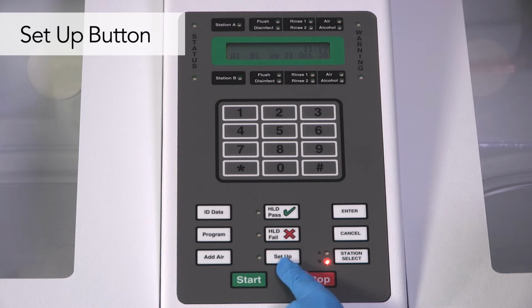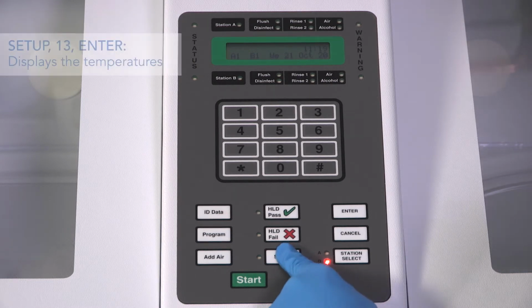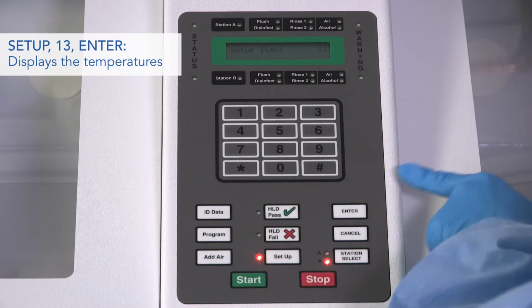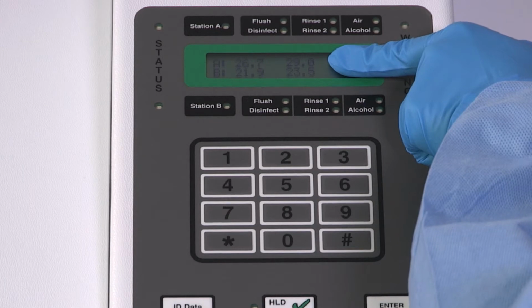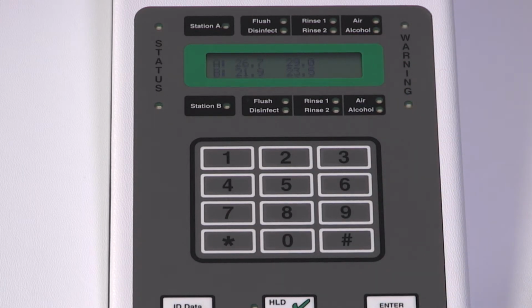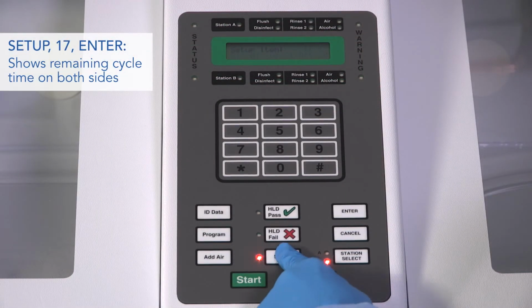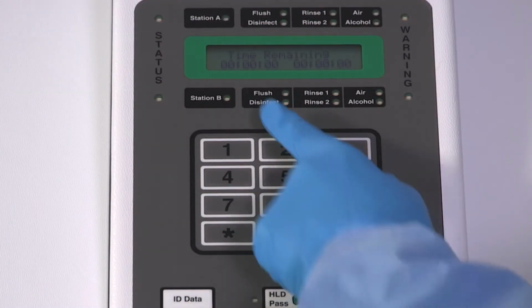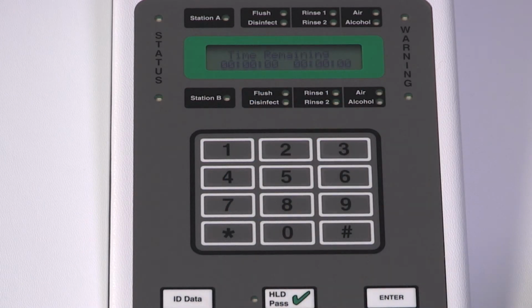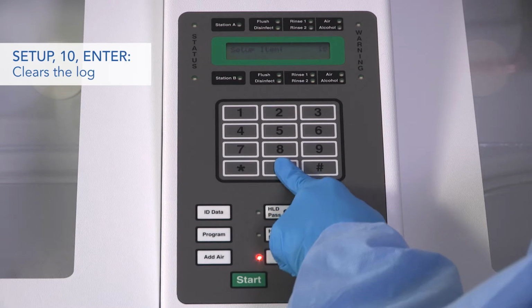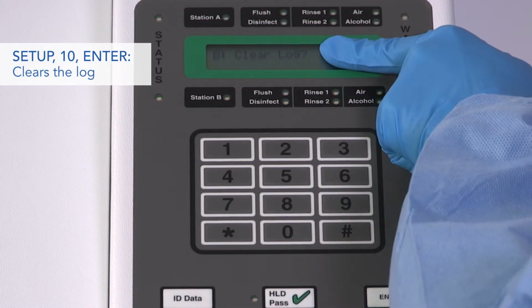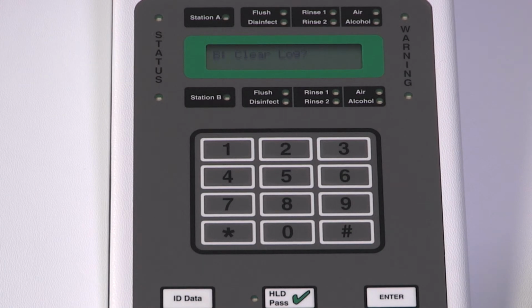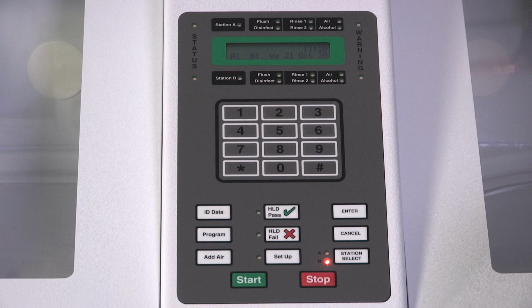The Setup button allows you to access various functions, including Setup, 13, Enter, which displays the basin temperature on the left and the incoming water temperatures on the right in Celsius for both stations. Setup 17, Enter, shows the remaining cycle time for both stations. Setup 10, Enter, clears the log for the selected station. The log or memory should be cleared on a regular basis, depending on your volume. This refreshes the memory and helps prevent printing errors. Prior to clearing the log, ensure all cycle data logs are printed out.